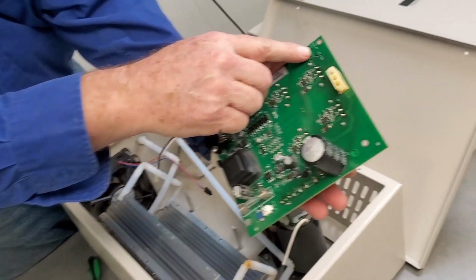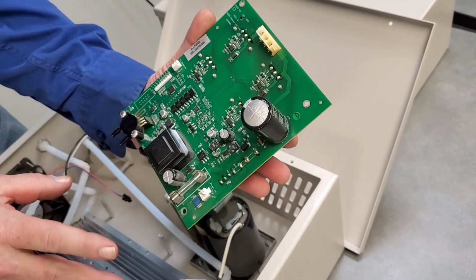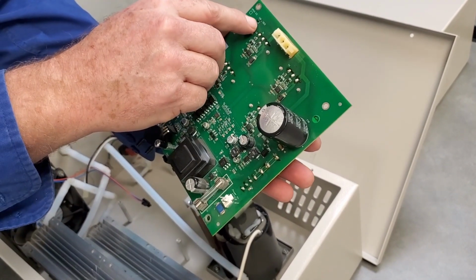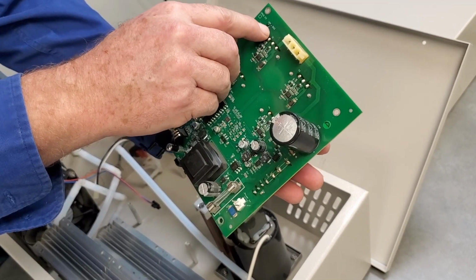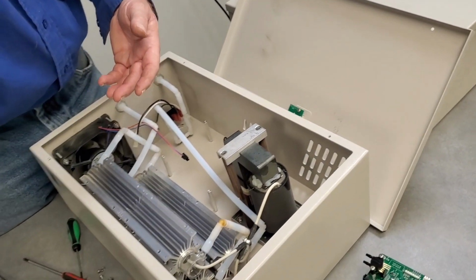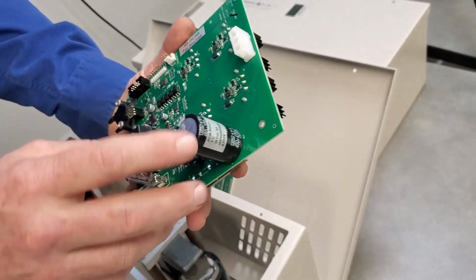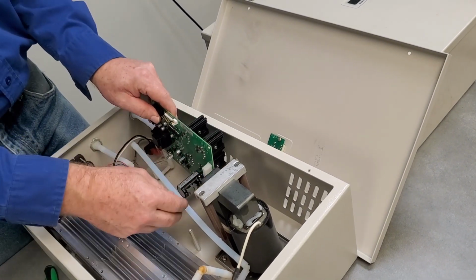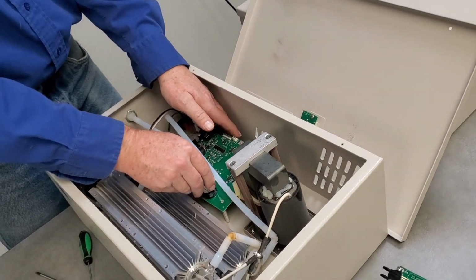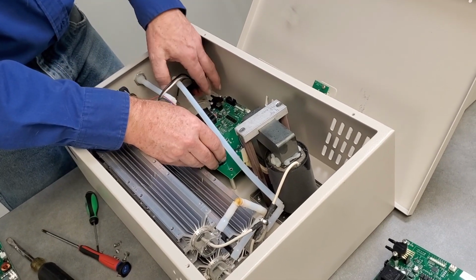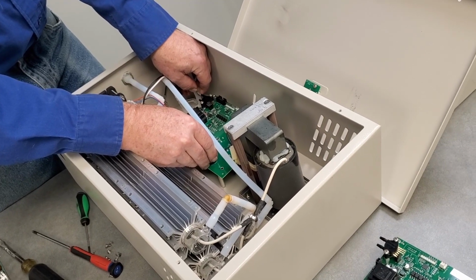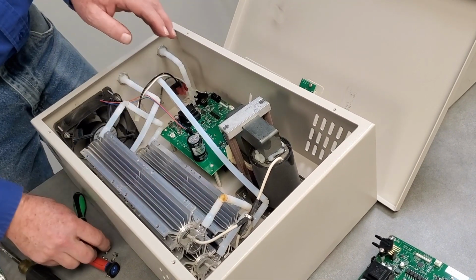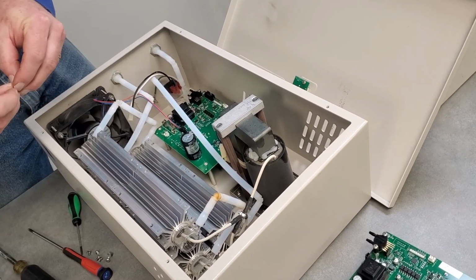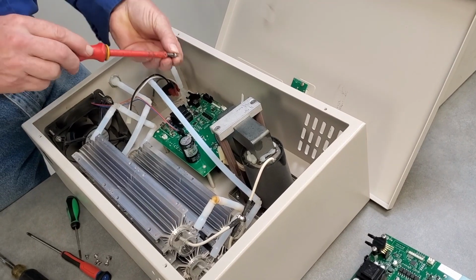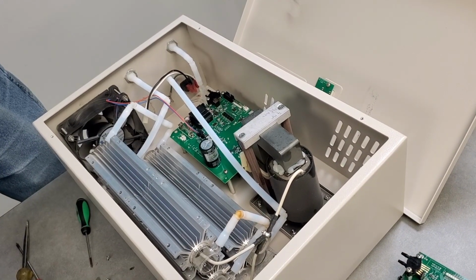This particular unit, the circuit board here, they're programmed to work with specific type cells. Since this is a DG-3, we want to make sure that the board is the correct board for this. It's checked off for DG-3. The new one that I've got here is checked off for a DG-3. So we're going to replace this. Get it screwed on there first. Each of these has got a little lock washer. There we go, steel one over here.